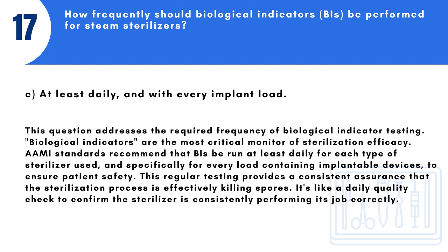Answer: C. At least daily, and with every implant load. This question addresses the required frequency of biological indicator testing. Biological indicators are the most critical monitor of sterilization efficacy. AAMI standards recommend that BIs be run at least daily for each type of sterilizer used, and specifically for every load containing implantable devices, to ensure patient safety. This regular testing provides a consistent assurance that the sterilization process is effectively killing spores. It's like a daily quality check to confirm the sterilizer is consistently performing its job correctly.